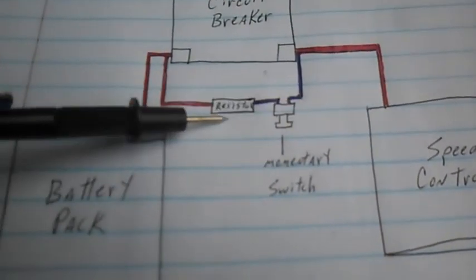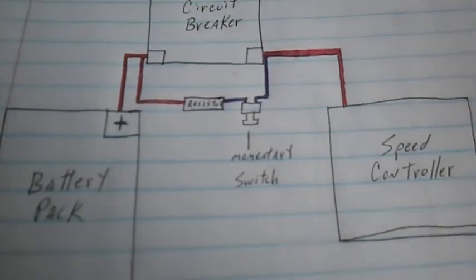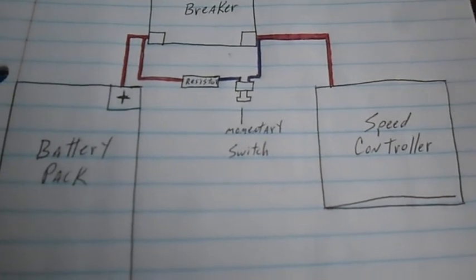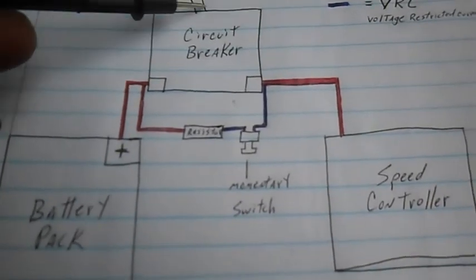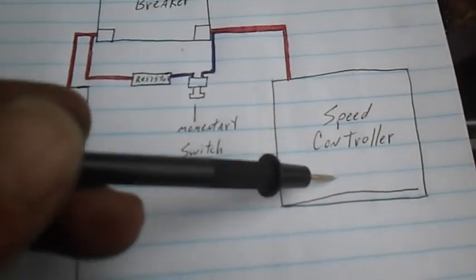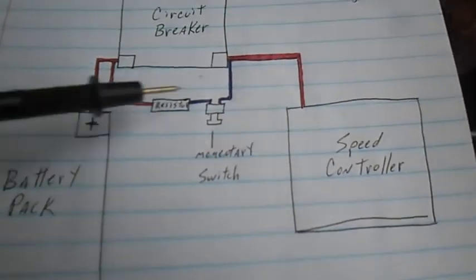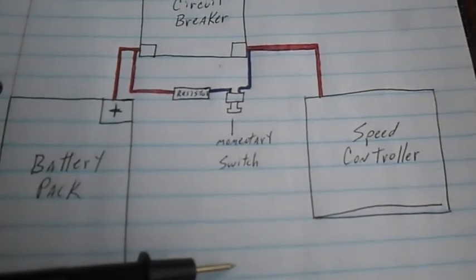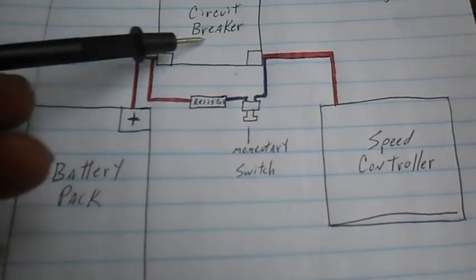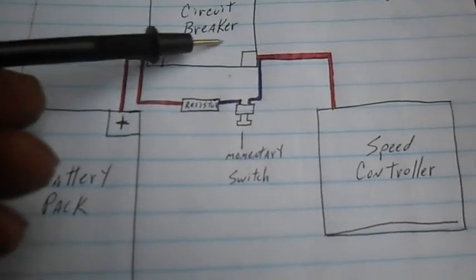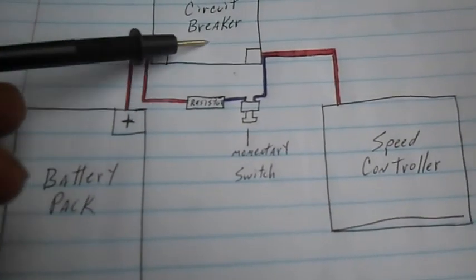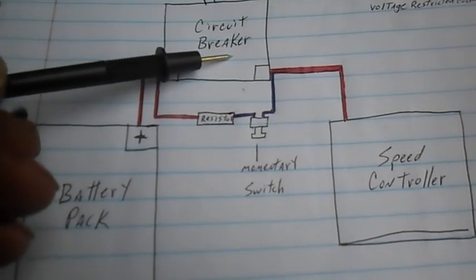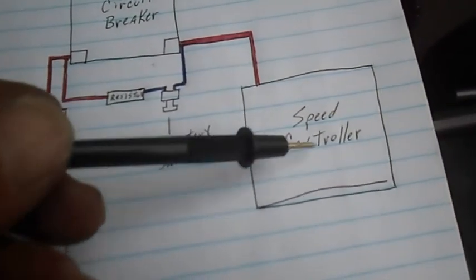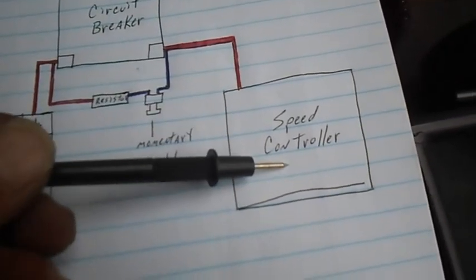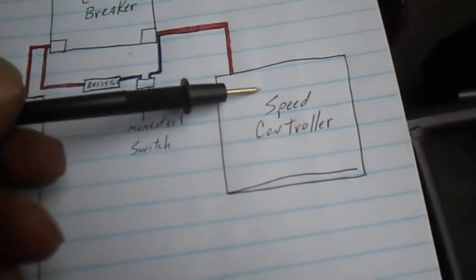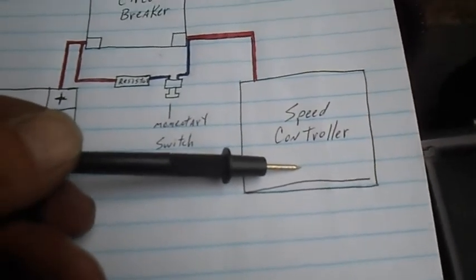Whereas without a precharge circuit, let's say the system's been down, you haven't used it for a couple of days or something. You go to use it, and you turn this breaker on, the capacitors in the speed controller are empty. So they want to suck up and draw a whole bunch of energy quick to fill themselves up. The switch in your circuit breaker is going to see that big giant surge of energy and could potentially damage the contacts in your circuit breaker. But also, the capacitors get that big giant surge of energy, it's called an inrush, and can blow out your capacitors if not the first time, over time.